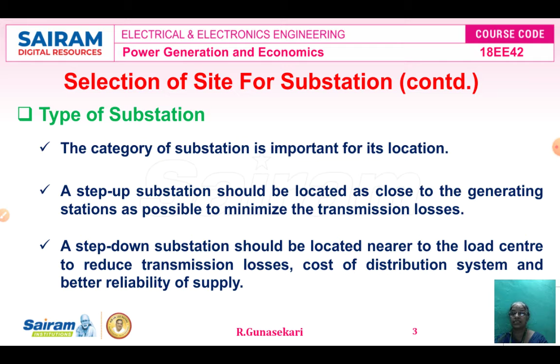The second factor is availability of suitable and sufficient land. The proposed land for the substation normally should be level and open from all sides. It should not be waterlogged, particularly in the rainy season. The site selected for the substation should be such that the approach of transmission lines and their takeoff can be easily possible without any obstruction. I mean, places nearer to the aerodrome, shooting practice grounds, etc., should be avoided.